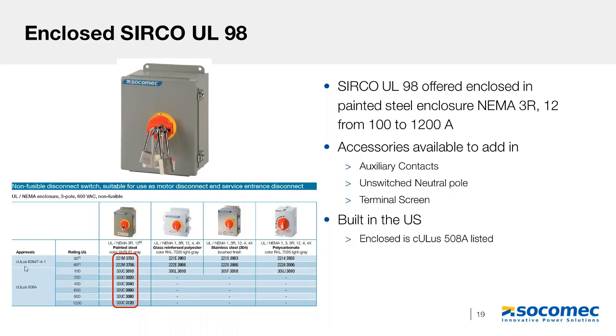So you can see here on the slide on the left-hand side under approvals, that standard is the same as the UL508 for the 30 to 60 amps, so motor disconnect applications. And then underneath that, you can see the 508A, which is an enclosed UL98 switch for feeder applications. So you can see how selecting these standards can be very important. It can be a little bit tricky at first for sure, but making sure that you have the right switch for the right application is important. And I know that UL508 is smaller and typically more cost effective, but it can't be used in those feeder circuit applications. And it's very important that you use a UL98 switch instead.